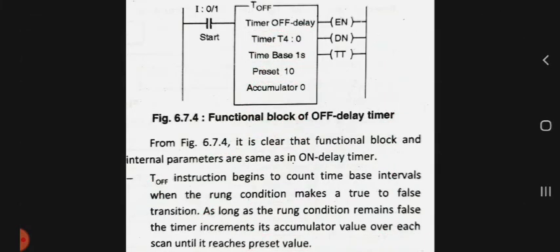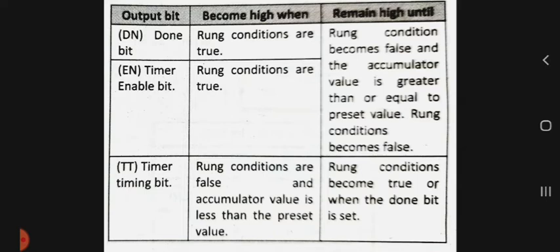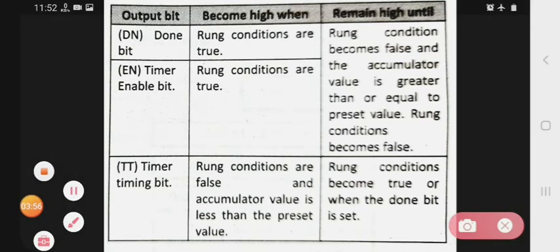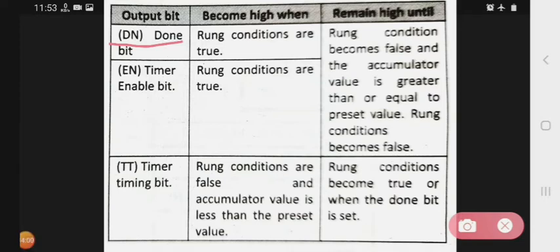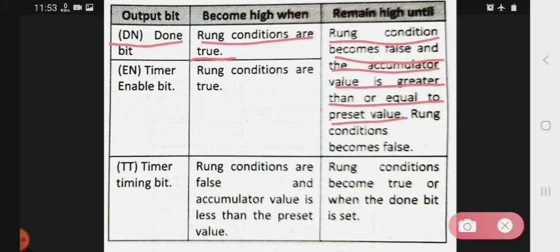Now let's see the output bits in the functional block diagram of the off delay timer. The first bit is DN, that is the done bit. In the off delay timer, the done bit becomes high when the rung condition is true, and it remains high until the rung condition becomes false and the accumulator value is greater than or equal to the preset value. When the rung condition becomes false and the accumulator value reaches the preset value, the done bit turns off.